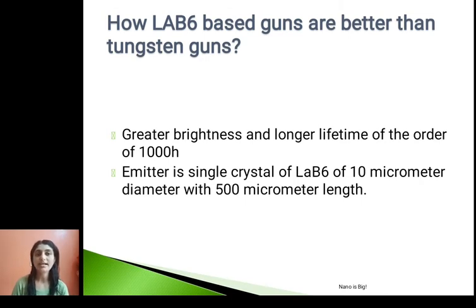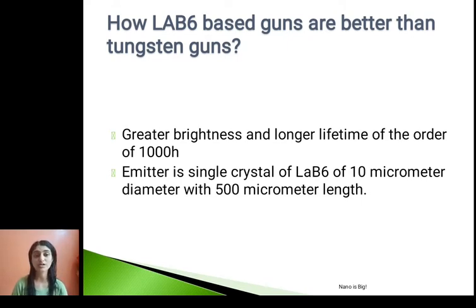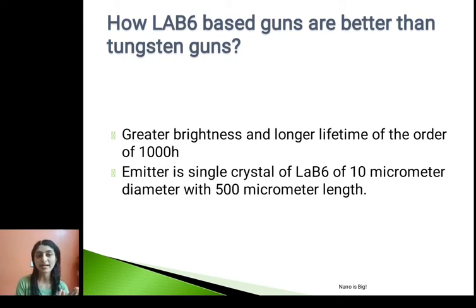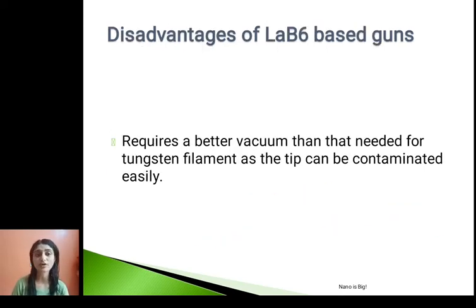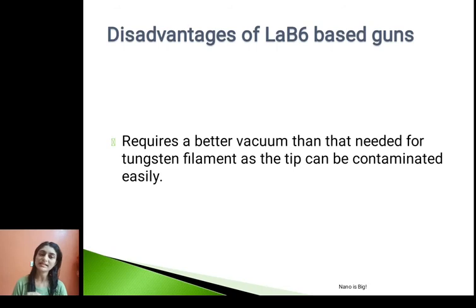LaB6 guns are better than tungsten guns because they have greater brightness and a longer lifetime of the order of 1,000 hours. The emitter used here is a single crystal of LaB6 of 10 micrometer diameter and 500 micrometer length, whereas in tungsten guns we have a tungsten wire. The disadvantage of LaB6 based guns is that they require a better vacuum than that needed for tungsten filament because the tip easily gets contaminated.